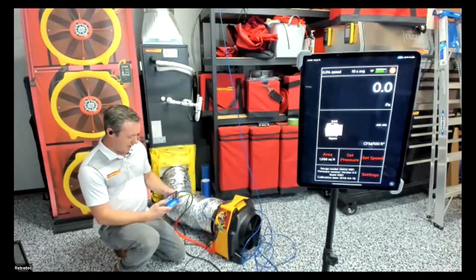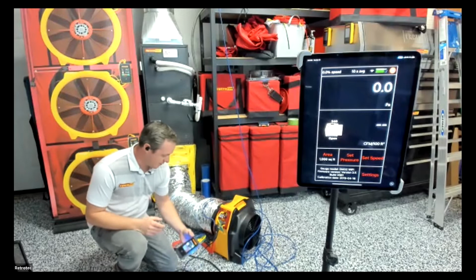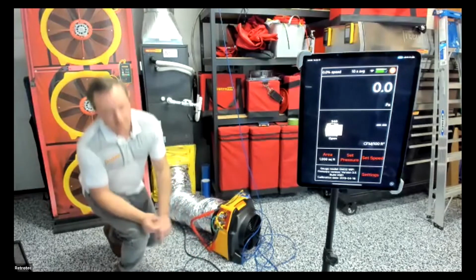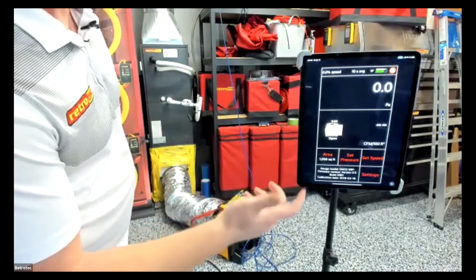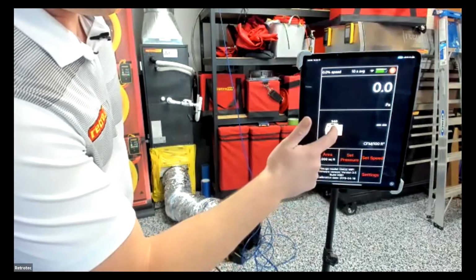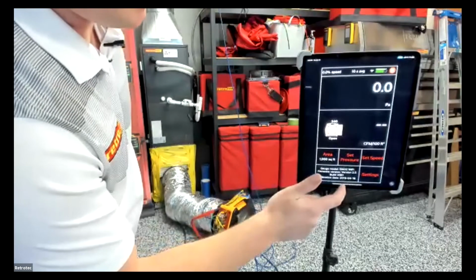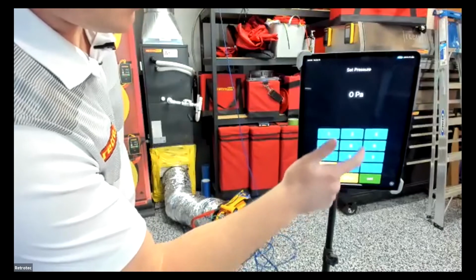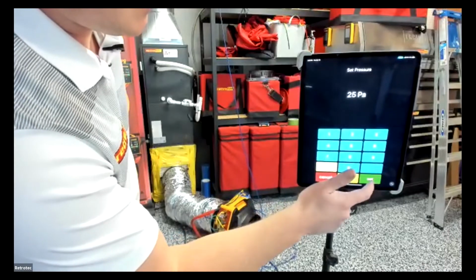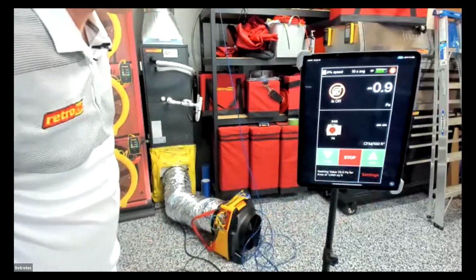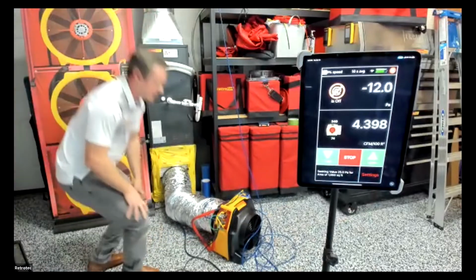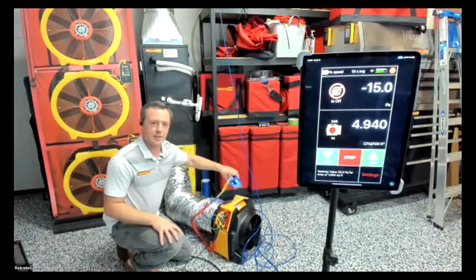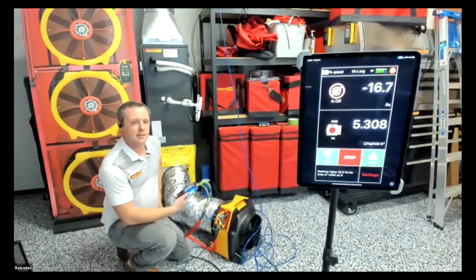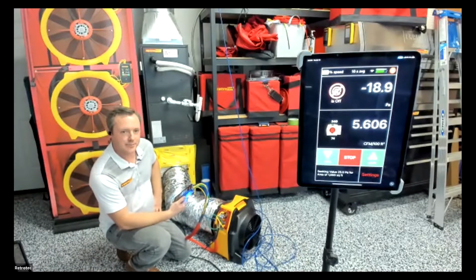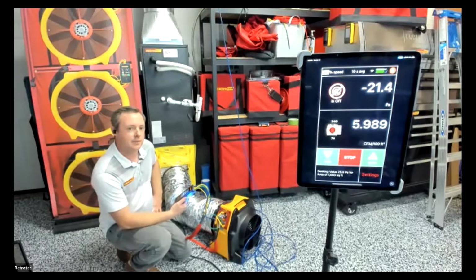So now we're ready to go. The way we're going to run this is, we test every system to 25 pascals. Let's get this on 74. There we go. We'll go to set pressure, 25, hit set. And I'm not sure if you can hear the fan kick on, but it is running. As you can see, we're getting our duct system down to pressure. It's seeking that negative 25. We're at about negative 20 now.